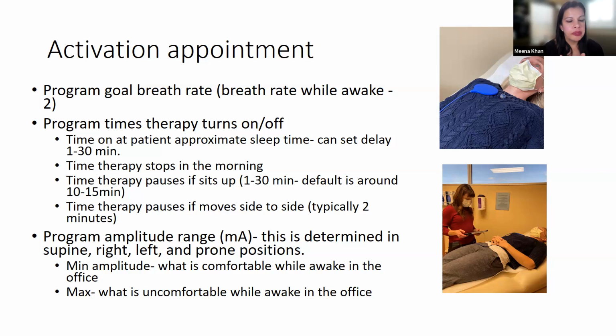You want to program the time the therapy should turn off in the morning. You want to program the time that it's going to pause if the patient sits up. Again, that can be anywhere from 1 to 30 minutes, with the default being 10 to 15. After this time has passed, it will reassess for the 3 parameters to restart therapy, which is time after falling asleep, pitch, and not moving, and then restart therapy. And then you can also put in the time where therapy pauses if they're moving side to side. Typically, we make this shorter, around 2 minutes, because usually they're just turning over. They're not really fully waking up. And so you can make this shorter before it reassesses for all 3 things and restarts therapy.